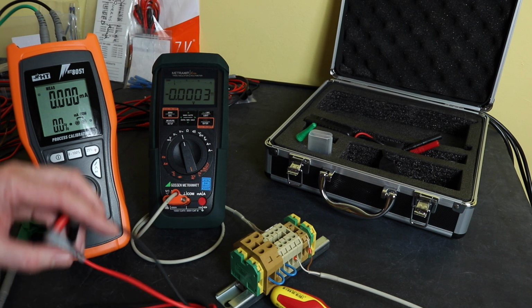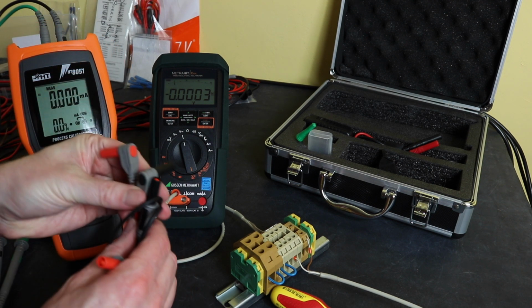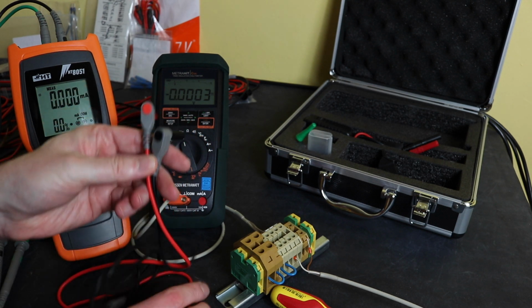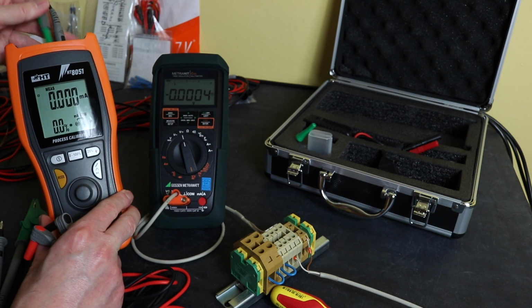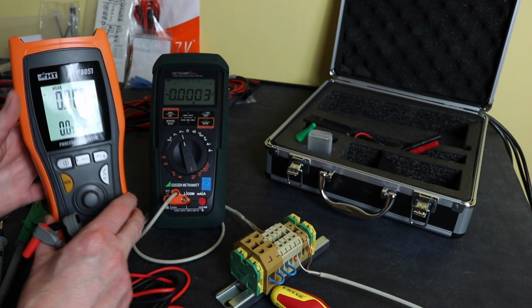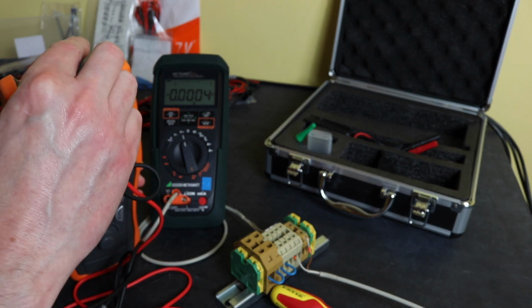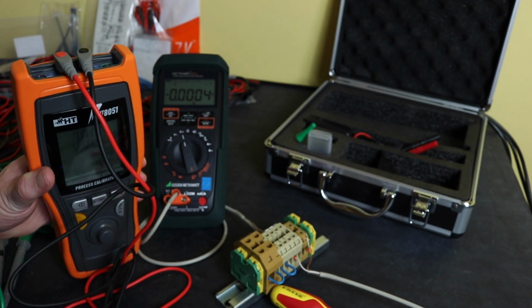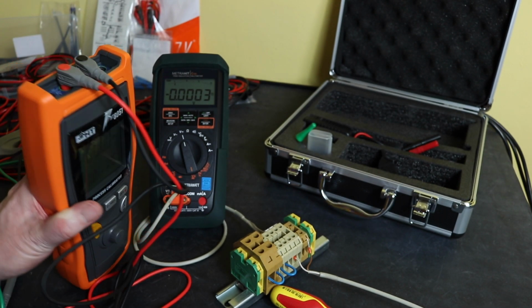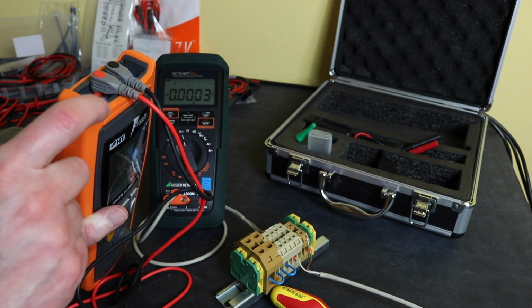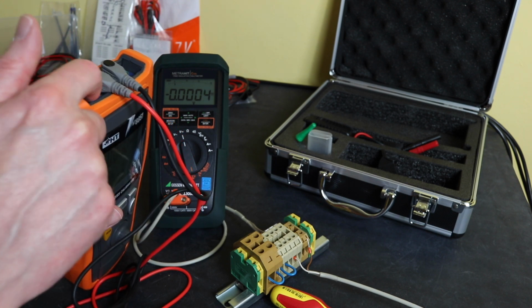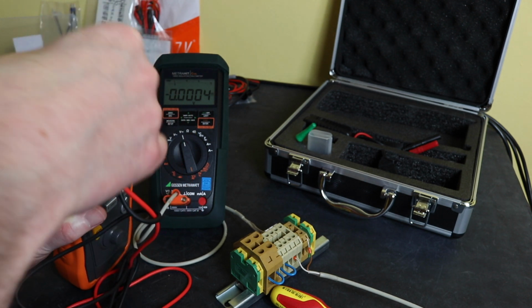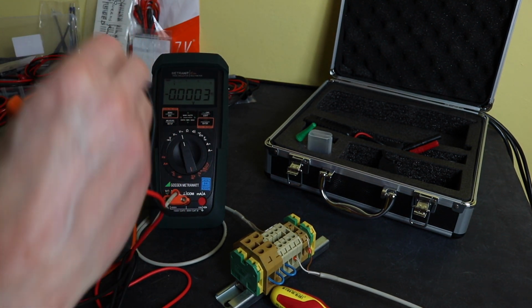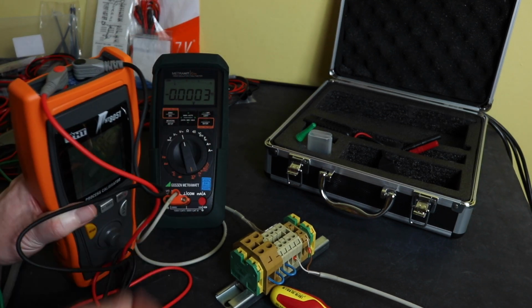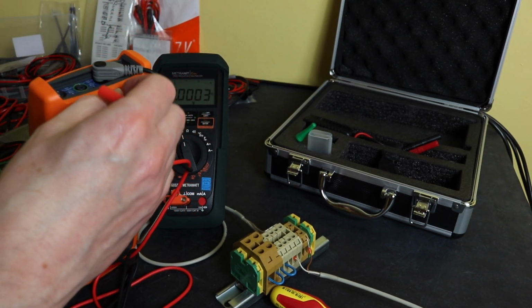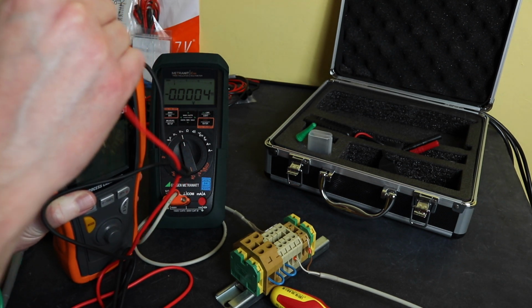However, the leads that come with it have a right angled plug, as you find on a lot of leads nowadays. So when I went to plug them in at the top, you can see they don't sit very well in the actual top of the meter, because the jacks are recessed down inside the instrument a little bit. You can push them towards the sides and get them a bit lower, but then they can become quite difficult to actually remove. So this is not the ideal option.